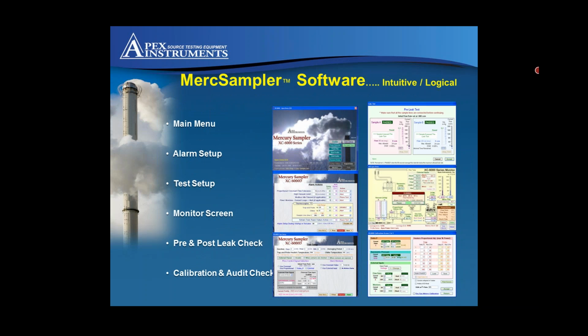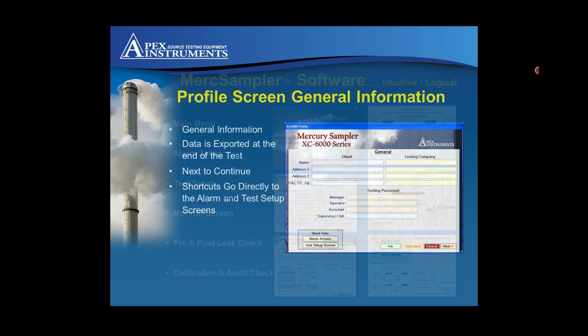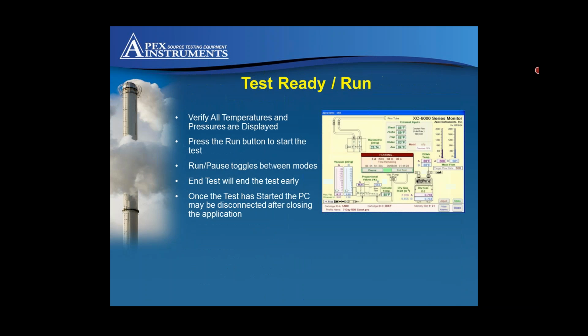Okay, so here are the different screens. Down on the left-hand side, we've got the main screen. Then the middle one is the core of setting up your alarms. You can see there are different ones. You set them for temperatures, and you put in a range. Once you set an alarm, you can either have it just alarm, or you can actually pause the console.